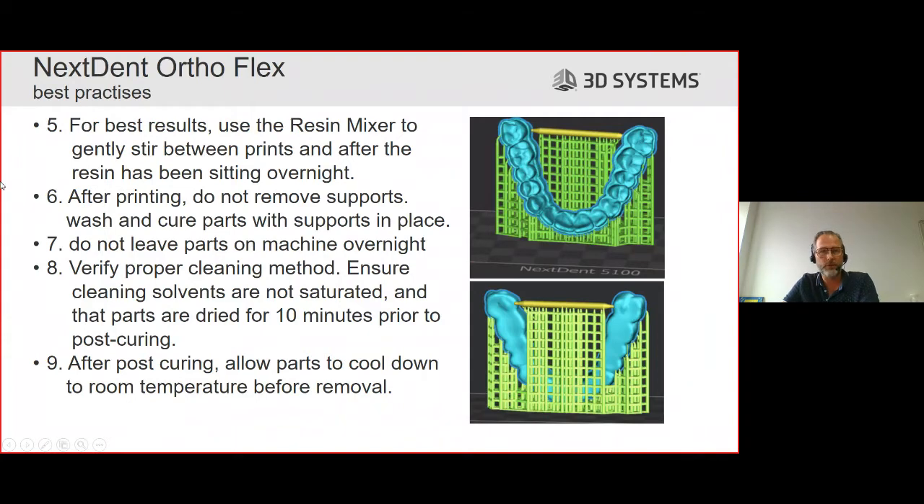For best results, use the resin mixer to gently stir between prints after the resin has been sitting overnight. If you want to leave the OrthoFlex resin in the resin tray overnight, that's not a problem. Before you do the next print, stir the resin. It's not so much that this resin needs a lot of mixing, but it also doesn't do any harm, and more importantly, we want to check for foreign bodies like small broken supports that could damage the membrane.